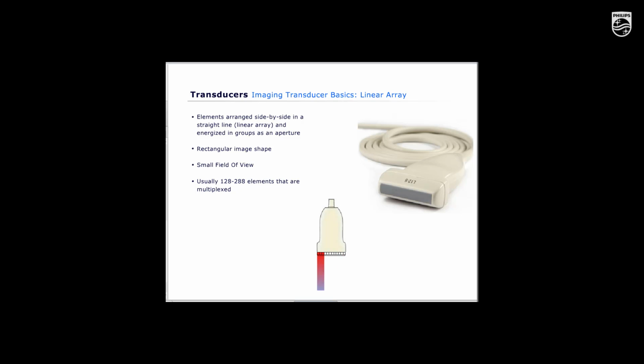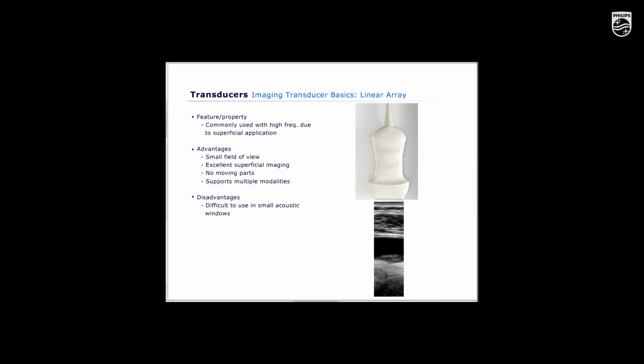Applying voltage pulses to groups of elements in rapid succession is referred to as electronic scanning. When the process repeats rapidly enough, a real-time presentation occurs. The number and size of the elements in combination with how the groups of elements fire impacts the number of scan lines, or line density, in the image. A 250 line density image has better image quality than a 128 line image, as an example.